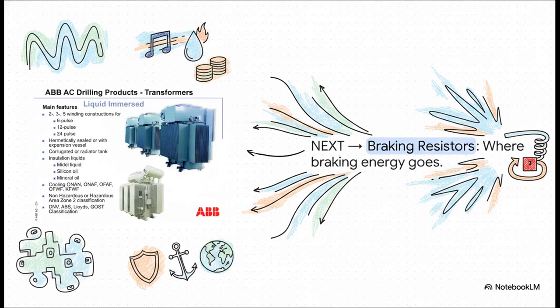So, before this explainer, liquid immersed transformers might have just been a generic gray box on a diagram to you. But now you know the 3 real design axes. You've got winding configurations setting your harmonic performance from 6-pulse up to 24-pulse. You've got insulation fluids trading off fire safety against cost, and you've got class society approvals constraining the entire physical build from day one.